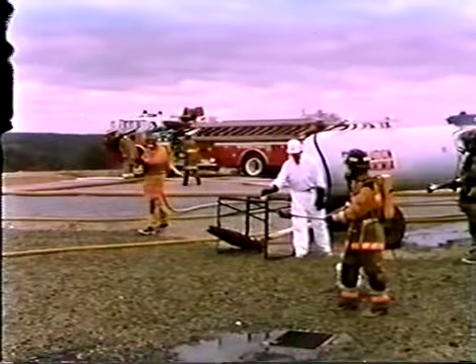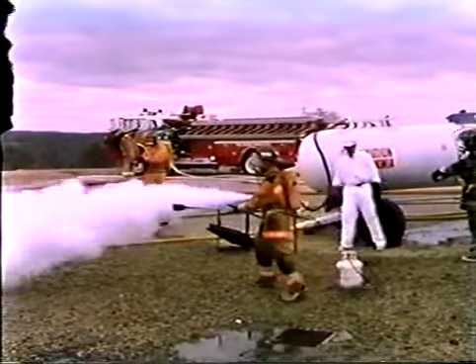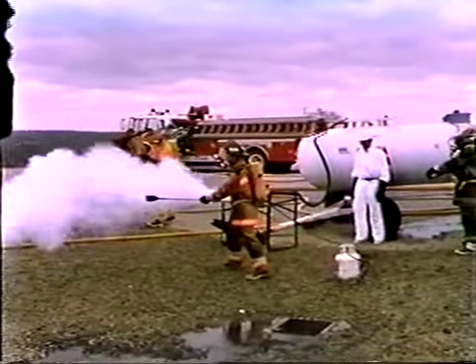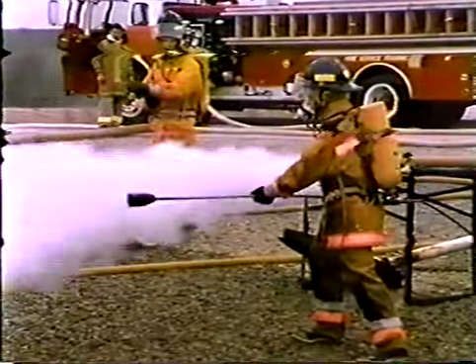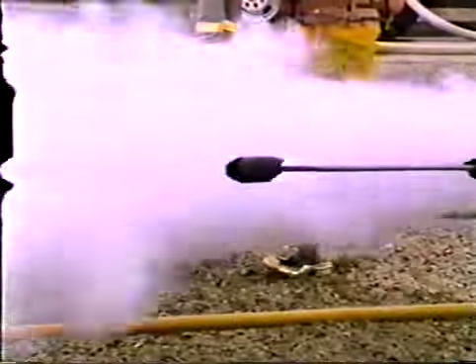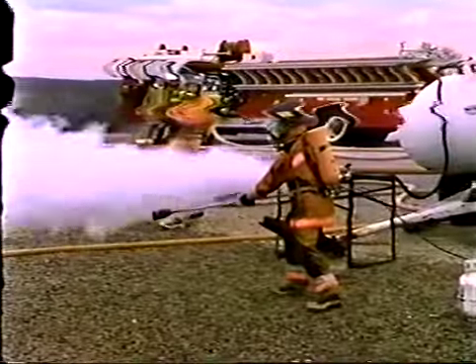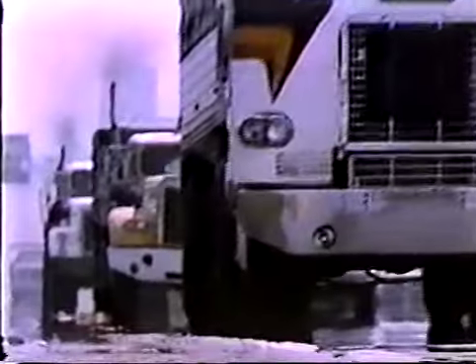Release outdoors is not usually a fire problem. There are seldom accumulations within the flammable range except in the proximity of large spills. There may be ignitable limits in discontinuous pockets, but higher than normal ignition energy is required. If vapors are ignited, the low flame propagation speed would preclude detonation. In a study of more than 500 outdoor anhydrous ammonia incidents by the National Transportation Safety Board, only three involved fire.